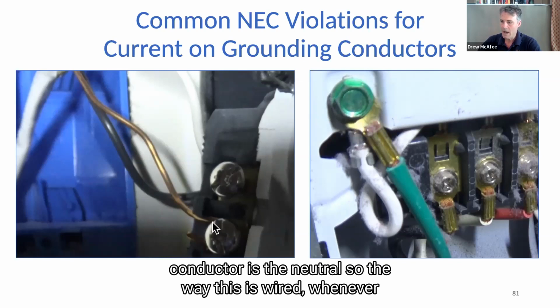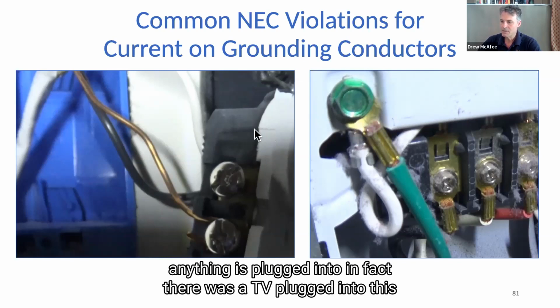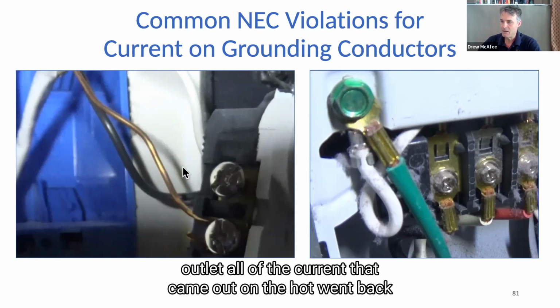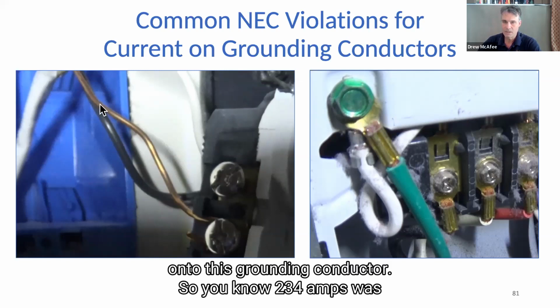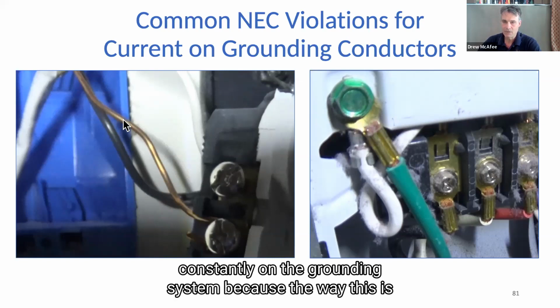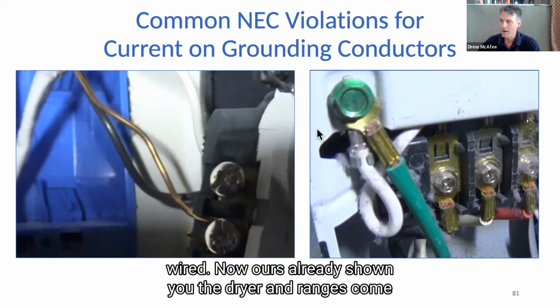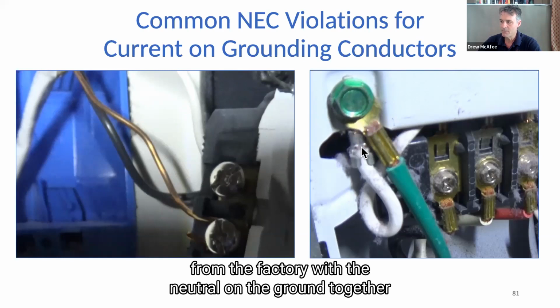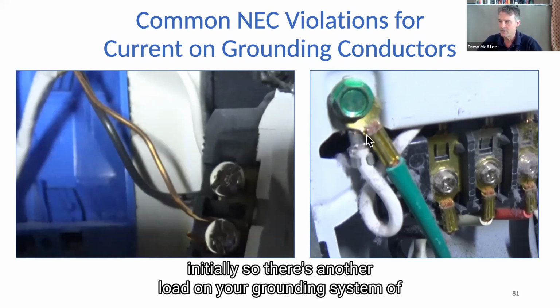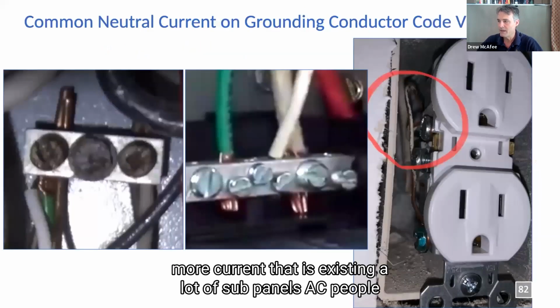The way this is wired, whenever anything is plugged into this outlet, and in fact there was a TV plugged in, all of the current that came out on the hot went back onto this grounding conductor. So 2, 3, 4 amps was constantly on the grounding system because of the way this is wired. Now, he already showed you that dryers and ranges come from the factory with the neutral and the ground together initially. So there's another load on your grounding system of more existing current.